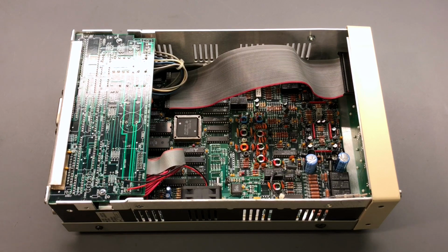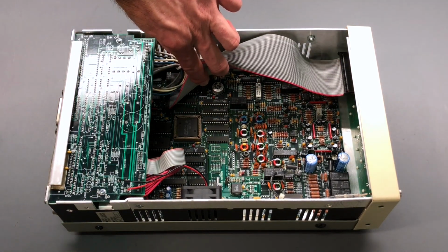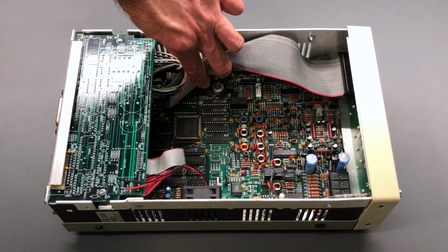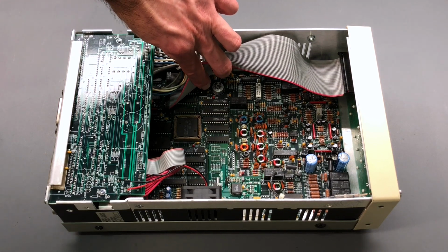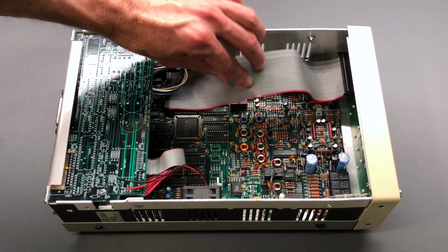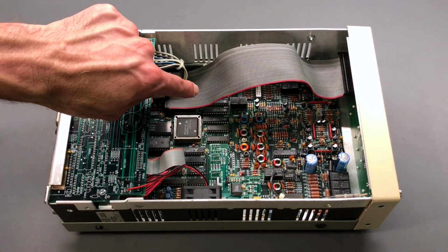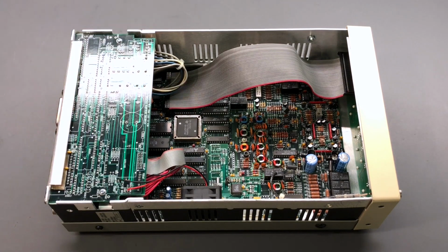So again, we're seeing that the frequency is off by a little bit, and that could be corrected. The cal byte that is related to the frequency is something that could be adjusted. And it can be done on the front panel. And over here, there is a jumper on the circuit board that is moved over, actually where it is right now, and that gives access to changing the cal bytes. If it's stored in the other position, that's the position that locks out the ability to change the cal bytes. It was already in the position for allowing changes, so someone else may have already been in there trying to change those cal bytes.